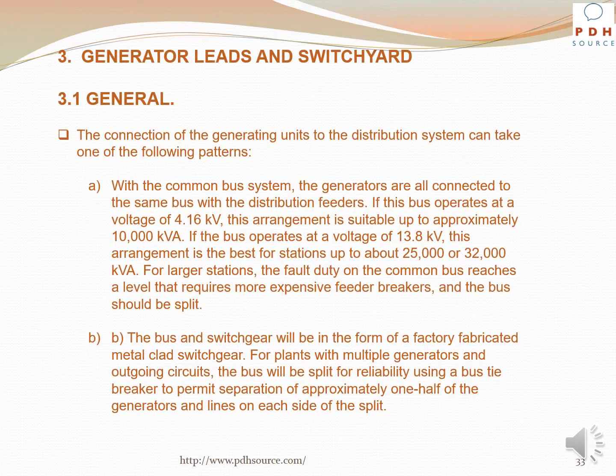Now, with regard to the generator leads and switch yard, the connection of the generating units to the distribution system can take one of the following patterns. With the common bus system, the generators are all connected to the same bus with the distribution feeders. If this bus operates at a voltage of 4.16 kV, this arrangement is suitable up to approximately 10,000 kVA. If the bus operates at a voltage of 13.8 kV, this arrangement is the best for stations up to about 25,000 or 32,000 kVA. For larger stations, the fault duty of the common bus reaches a level that requires more expensive feeder breakers, and the bus should be split.